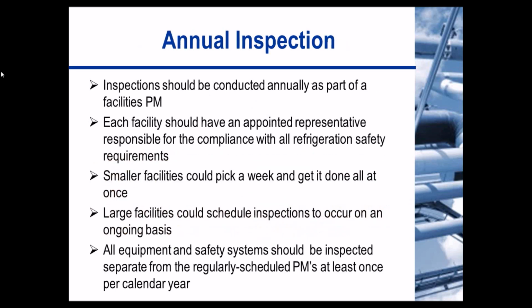Inspections should be conducted annually as part of a facility's preventive maintenance. Each facility should have an appointed representative responsible for compliance with all refrigeration safety requirements. Smaller facilities could pick a week and just get all these requirements done at the same time, where larger facilities should schedule inspections to occur on an ongoing basis. Now, all equipment and safety systems should be inspected separate from the regularly scheduled preventive maintenance at least once per calendar year.